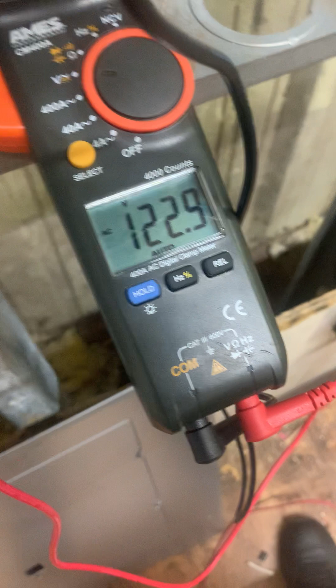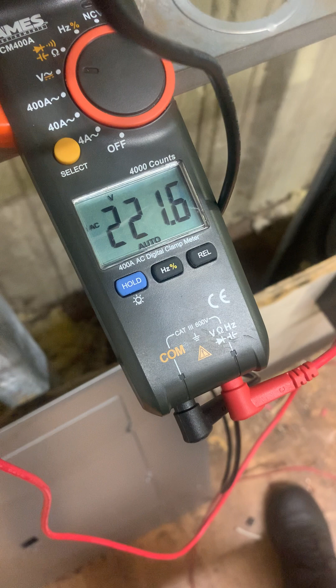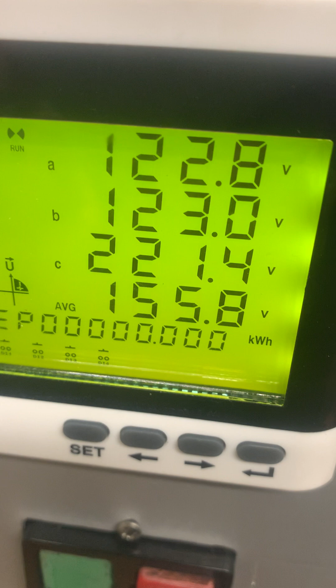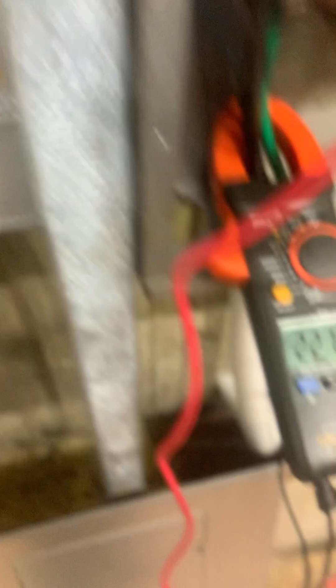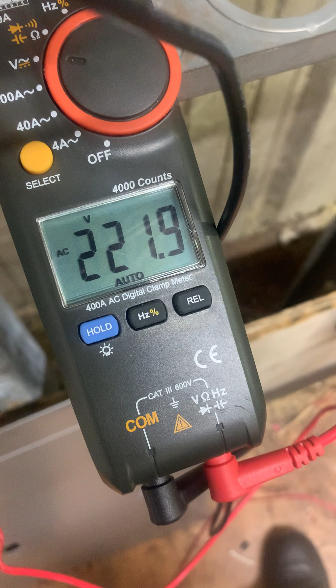123, yeah. But if I go from ground to B, to C, you see I got 222 volts. So my third leg from ground, straight from the converter, I'm at 220 volts. There must be, on the meter I get 221.6, so I'm kind of close. 221.9, 221, 222, somewhere over there.